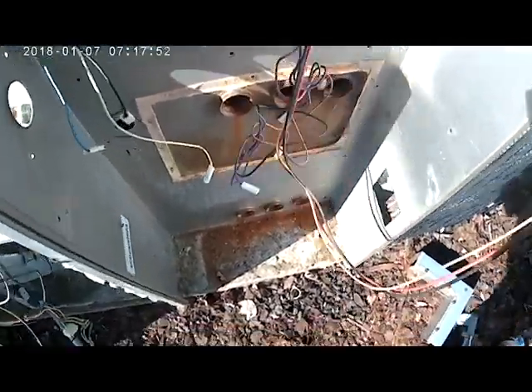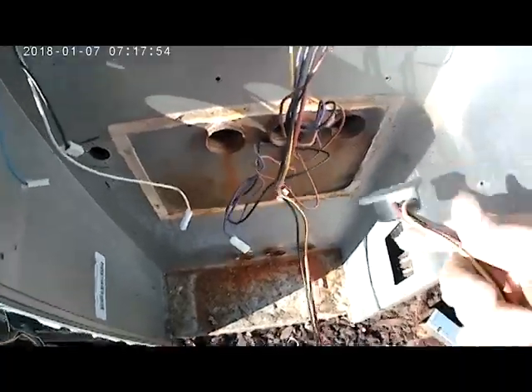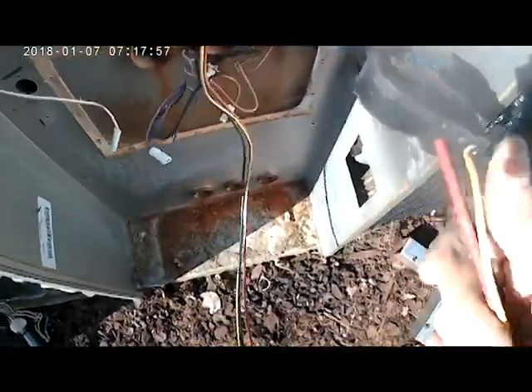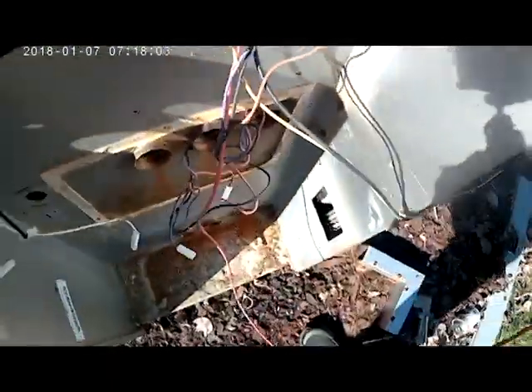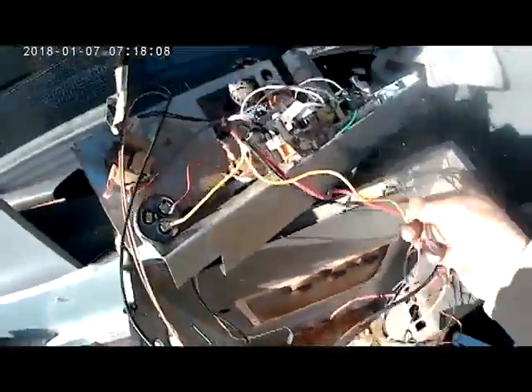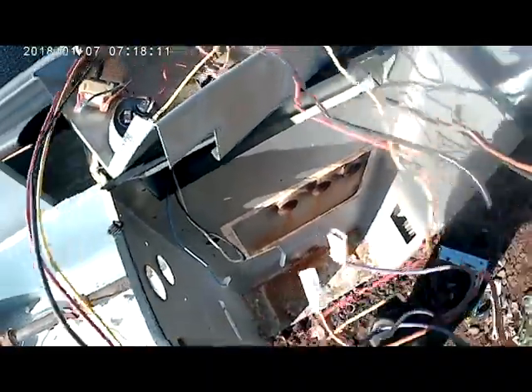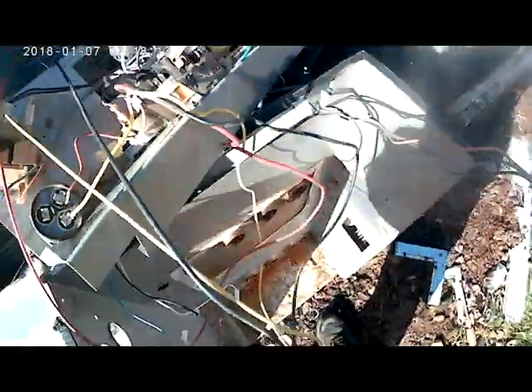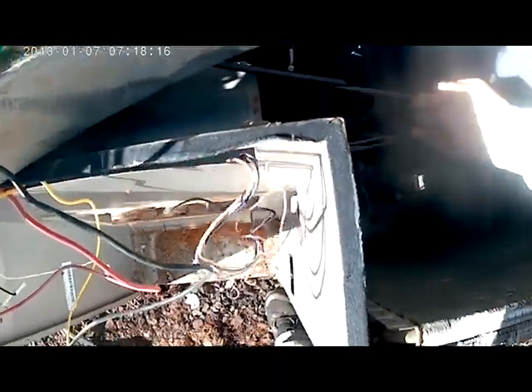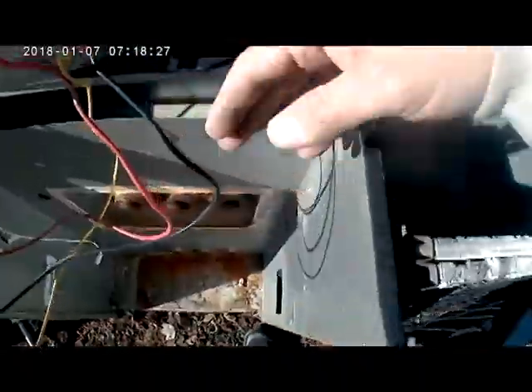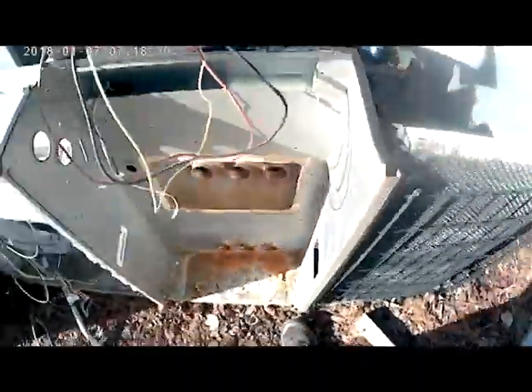Okay guys, these wires that were going through the front of the heat exchanger ended up being our compressor wiring. What I did is unhook it from the compressor, run it back up through, and we can put that over the top here. The other lines were our wires for our condensing fan motor. I took those off of the circuit board, and I can just run these down through here. It's only 3 wires to wire up, so it's pretty easy to know where they go. And if you get confused, you can always look on your wiring diagram -- it'll tell you where to go.